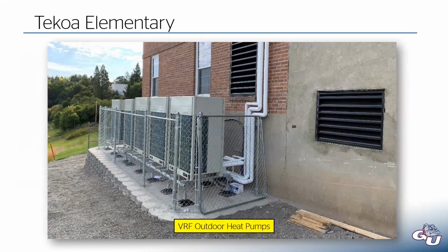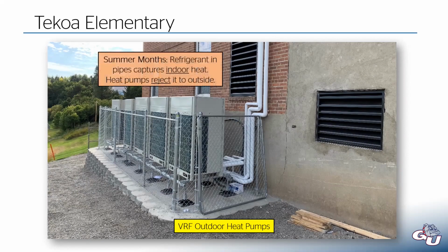All of these units get connected to some outdoor heat pumps. And so this is where the magic happens, I guess. So these heat pumps, what ends up happening in the summer months, when we're really hot outside and we need to cool down the building, these refrigerant pipes covered up in these three white sleeves are going to pull heat energy from inside the building, because the inside of the building is heating up because it's summer and it's hot. And so we'll capture that heat in the refrigerant that's running through those pipes, and then we'll reject it to the outside. And after the refrigerant rejects the heat, it'll go back into the building where it'll pick up heat again, and it just keeps doing that as needed.